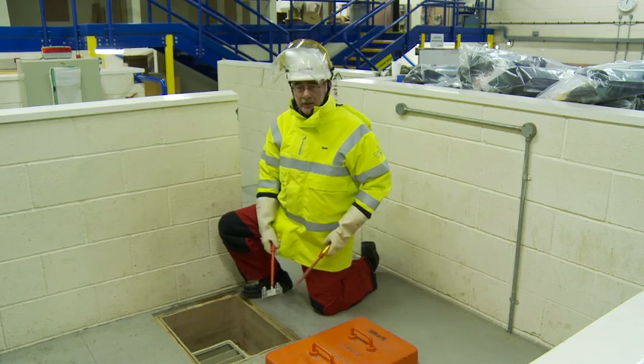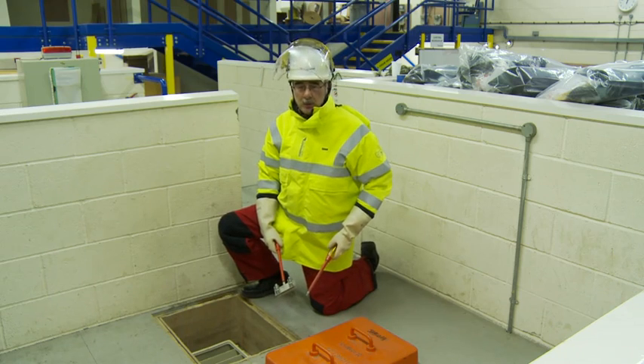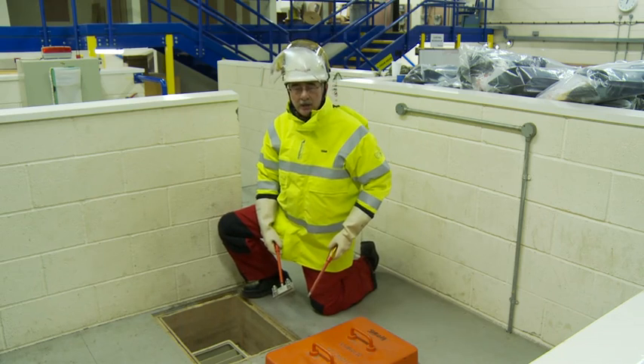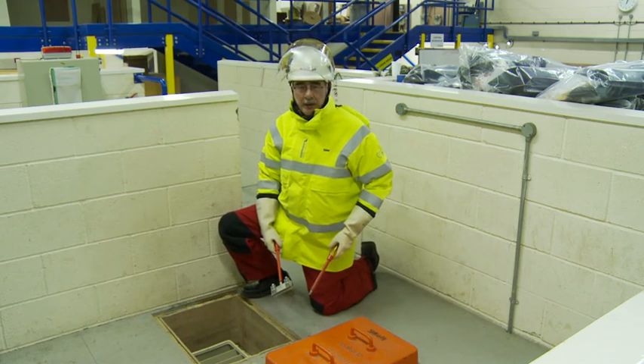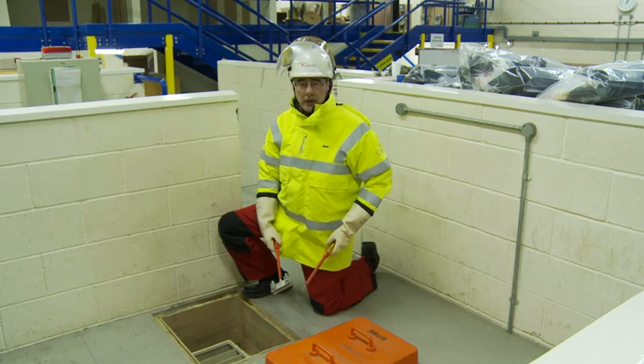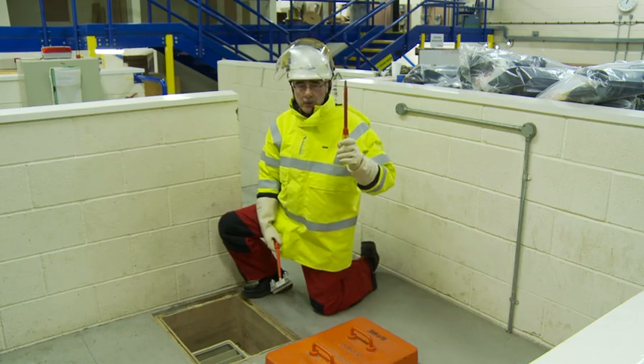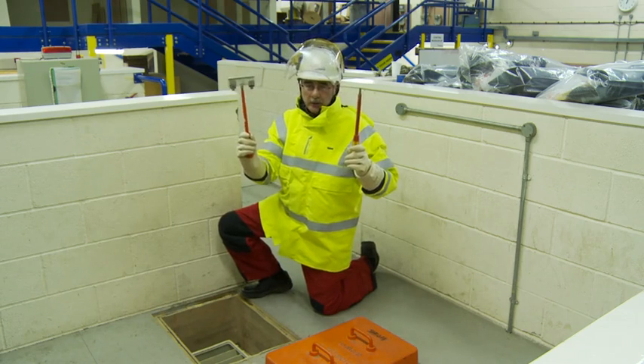If your feet are on the edge of the bell housing, you're potentially exposing them to something like 100 cals of energy. Increase that distance to 500mm and that reduces to less than 25. So when operating on link boxes, please use long screwdrivers where you can and long linking tools.